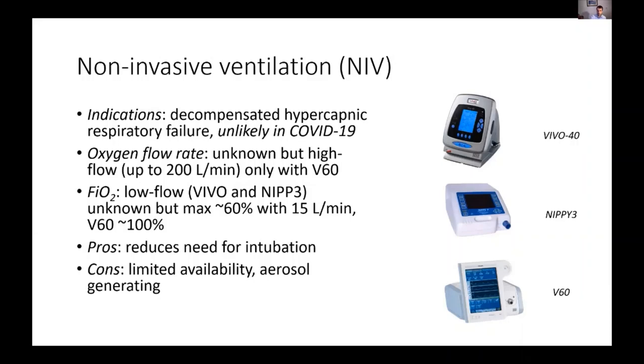Again, it can be delivered by a variety of machines, either low flow or high flow. The advantage of the high flow machine is that you can deliver higher flow rates and higher oxygen percentages. In reality, we haven't needed to use this very much in COVID because we've mostly seen type 1 respiratory failure. We tend to use this more in patients with exacerbations of COPD, and often there we don't need to deliver these very high levels of oxygen. So the lower flow machines such as the VIVO-40 or the NIPPY3 machine are perfectly adequate.